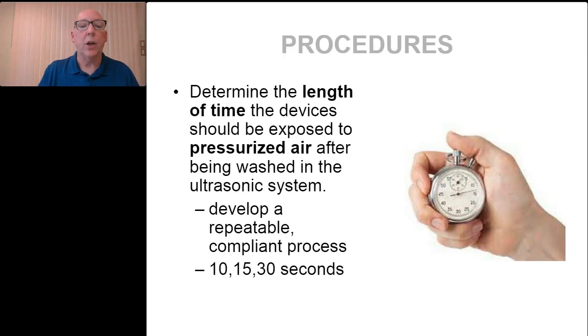Second, they determined the length of time the devices should be exposed to that pressurized air, right? As I mentioned during the survey, people were using pressurized air from 1 second to 60 seconds. So what the authors in the study did was use pressurized air and develop a repeatable, compliant process. They used pressurized air for 10 seconds, 15 seconds, and 30 seconds. And then they weighed all of the arms again after each of those time intervals, on a very sensitive weight scale, to determine if there was any moisture left in those arms after using compressed air for 10 seconds, 15 seconds, and then 30 seconds, to produce that benchmark and to see how much water was left in those devices.